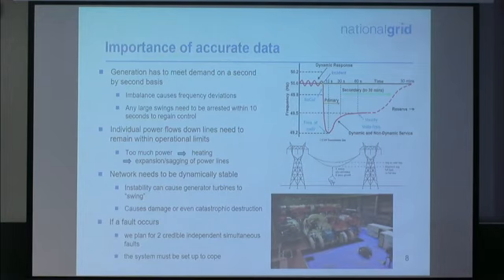So imbalance causes frequency deviations. We have about 10 seconds to arrest a large frequency deviation swing before it becomes uncontrollable. Automatic things ought to kick in after about half a second, so there are automatic generators on the system, but operators will need to take action immediately they see a very large frequency deviation either up or down, in order to ensure that nothing happens like an exploding generator or a national blackout.